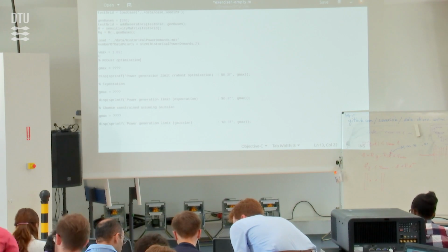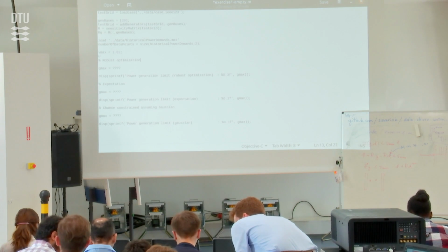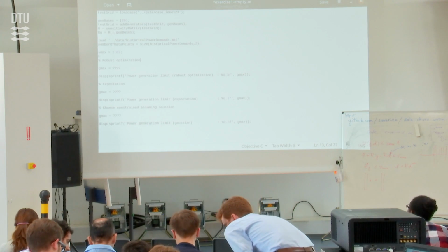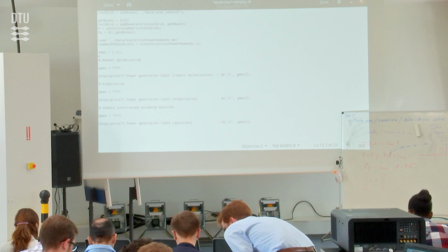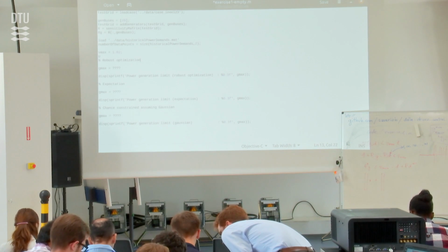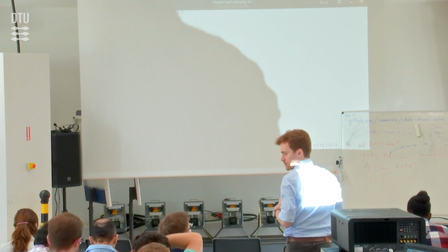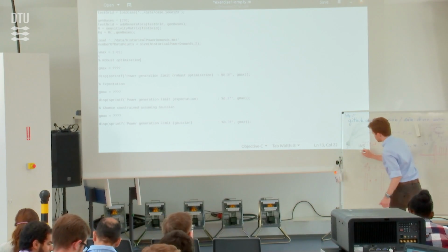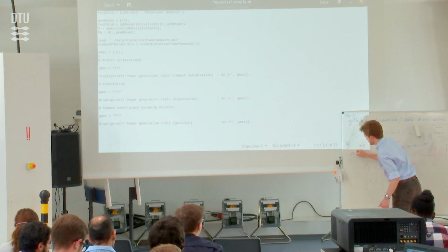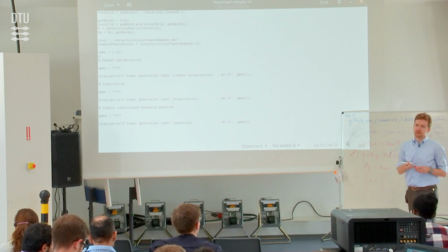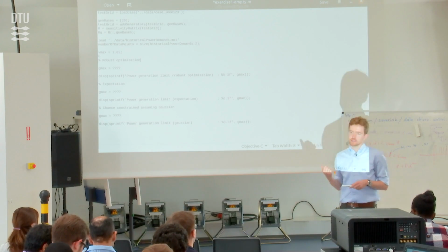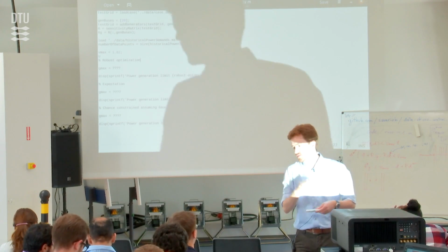Okay. Because this is basically the limit at every bus, for the voltage, for 1 per bus. You want the voltage to be satisfied for every bus, and so it's the smallest of that one. So go back to the output. The smallest of this element, which, I can tell you where it is, go up a bit, 1.4. Yeah, that one. Oh. Okay. Because these are 55 constraints, and they all need to be satisfied. For them to be all satisfied, you have to take the smallest of the G max, the one that satisfies them all. Okay? So I can just write the min function?